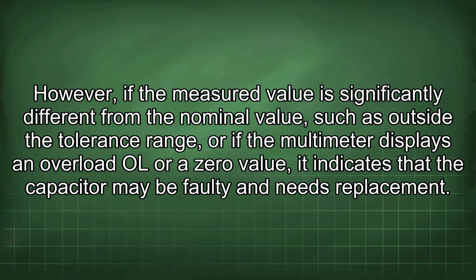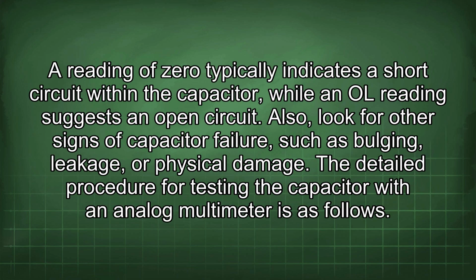faulty and needs replacement. A reading of 0 typically indicates a short circuit within the capacitor, while an OL reading suggests an open circuit. Also, look for other signs of capacitor failure, such as bulging, leakage, or physical damage.